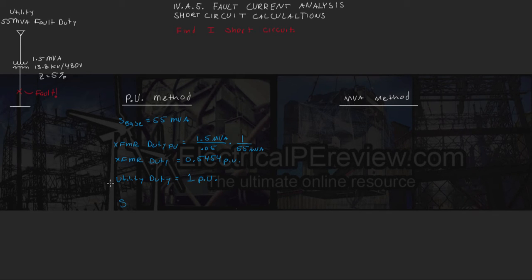Anytime we're dealing with short-circuit calculations, our complex power values are always going to be the sum of the reciprocals in series, and then they're going to just add normally in parallel. Since we've got our utility up here and our transformer, these are in series, we're actually going to add the inverse of the reciprocal sums.